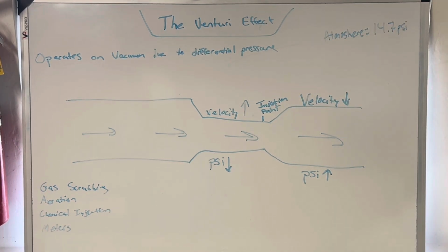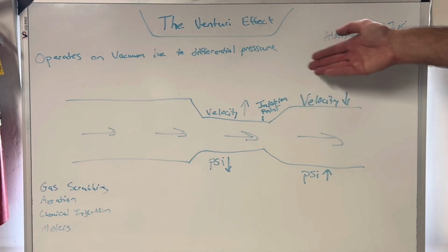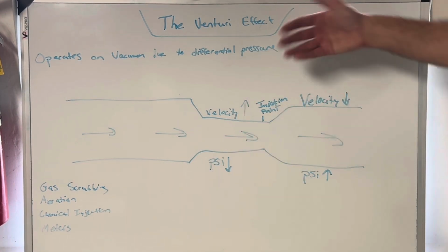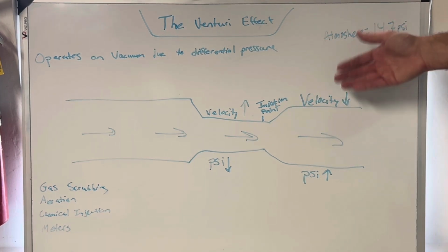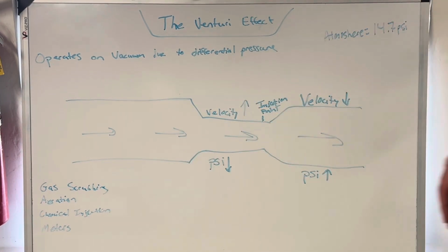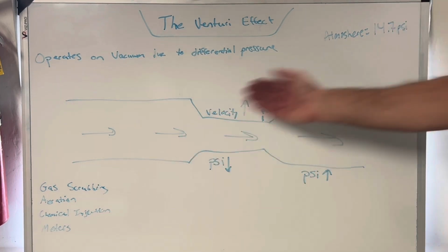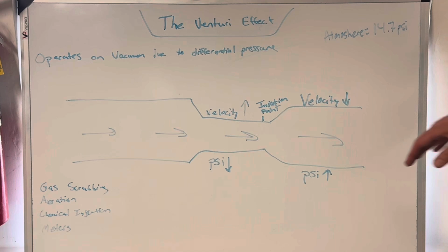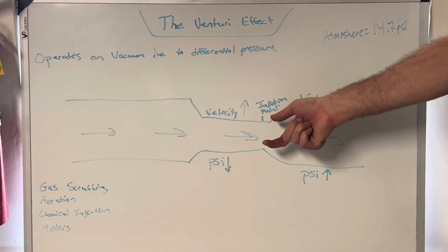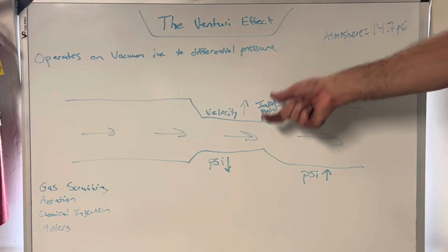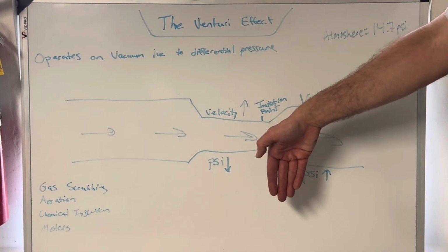So, when we are using the Venturi effect to add something, when we're metering, we're not adding anything, but when we're adding something to it, in case we're siphoning gas, like a nasty gas off to go to a scrubber, or we're adding air, or we're adding chlorine, what happens is, in this constriction, it's going to drop to a certain pressure that should be lower than whatever it is we're putting in, okay?